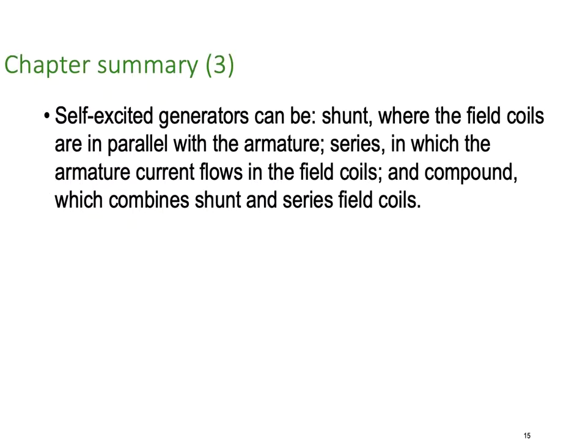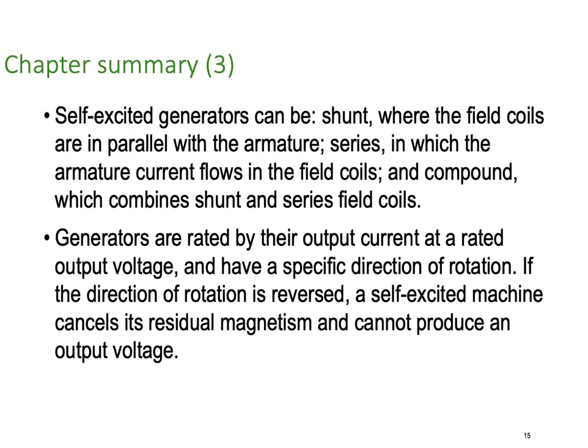Self-excited generators can be shunt, where the field coils are in parallel with the armature; series, where the armature current flows through the field coils; or compound, which combines both shunt and series field coils. Generators are rated by their output current at their rated output voltage. Remember, we'll have to put more power in than we'll ever get out because of losses. If the direction of rotation is reversed, a self-excited machine cancels its residual magnetism and cannot produce an output voltage. That's a trick for beginners.